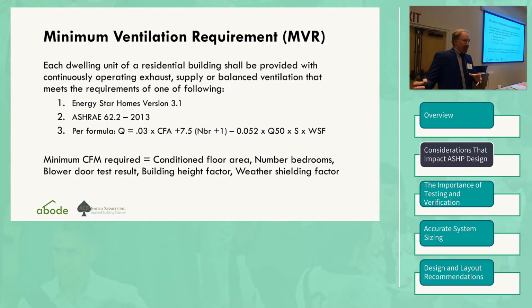So we've gotten away from a house has to breathe. Now we're building it tight and we're ventilating right. We know what the minimum ventilation rate is for every single home. We, as HERS raters, when we leave a home, when we test out a new home, we've actually got to set the fan to meet the MVR, the minimum ventilation rate for that home. The MVR is determined by, typically one of those two formulas. Well, the bottom one is probably more common now.